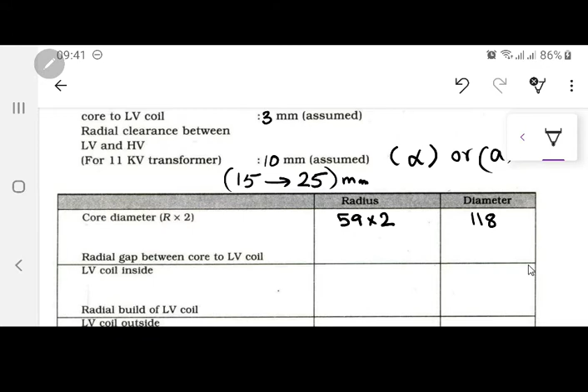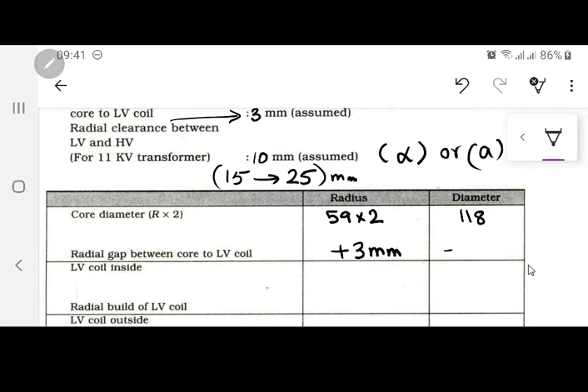So the radial gap between the core and the low voltage coil, what we have kept, is plus 3 mm. This is that radial gap between these. And here we are going to add 3, or 6 in the last column, which is diameter. So this has to be plus 6 mm because this is on both sides. It's a cylinder. So for the low voltage coil inside diameter or radius, this 2 is just telling you that it is the radius, otherwise you don't have to multiply or add it. So this becomes 59 plus 3, which equals 62 mm, and here this becomes 124 mm. This is the inside diameter of the low voltage coil.